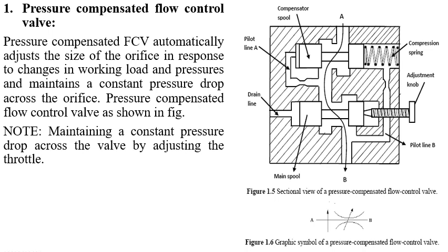See, pressure compensated flow control valves overcome the difficulty caused by the non-compensated flow control valves by changing the size of the orifice in relation to the changes in the system pressure. This is accomplished through a spring-loaded compensator spool that reduces the size of the orifice when pressure drop increases.